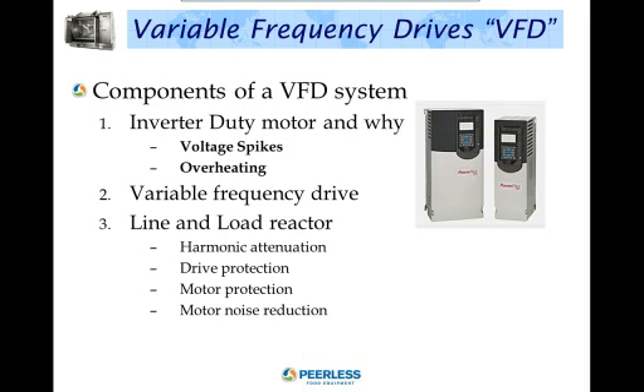Overheating. Inverters allow standard electric motors to be fed at simulated low frequencies, letting the motor turn at low speeds. This means the shaft-mounted cooling fan of the motor is also turning at low speeds and not delivering enough cooling air. Inverter duty motors are either rated to operate at higher temperatures or have a constant speed auxiliary fan which provides cooling at low speeds. The variable frequency drive generates the power to be transmitted to the inverter duty motor.